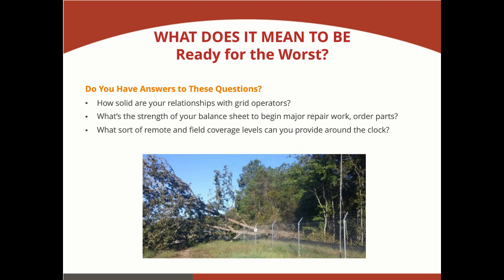The next question is really good, because when you think about a weather event that hits a very large territory or is very severe, it can cause extreme damage. It's not what you're used to running into daily, like one ground fault or a lightning strike taking out 20 solar panels. You could end up needing true construction work—racking tables collapsed or hundreds of modules removed from racks due to wind or other events. Then it's not just two technicians fixing something in a morning; you actually need dozens and dozens of construction personnel mobilized to rebuild portions of your PV plant.